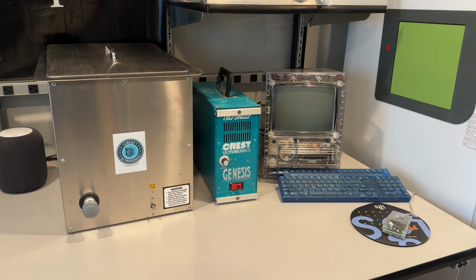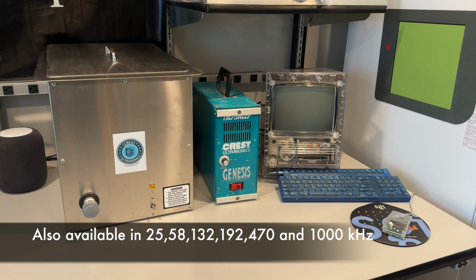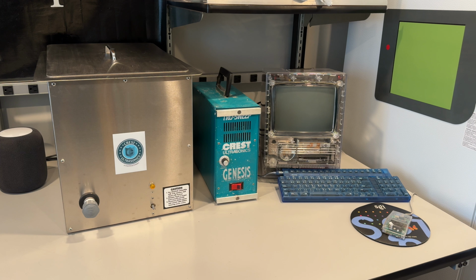It's equipped with 40 kilohertz transducers designed for more aggressive cleaning on less sensitive parts. There are other models that run at higher frequencies for more sensitive parts. From the model number, I think there are 6 of them, but I haven't opened up the tank to confirm that. The tank has a heater with a temperature range of approximately 60 degrees to 250 degrees Fahrenheit.